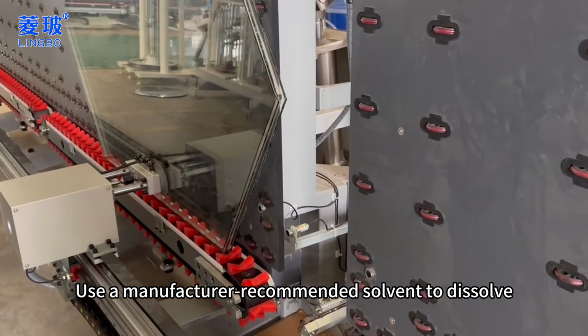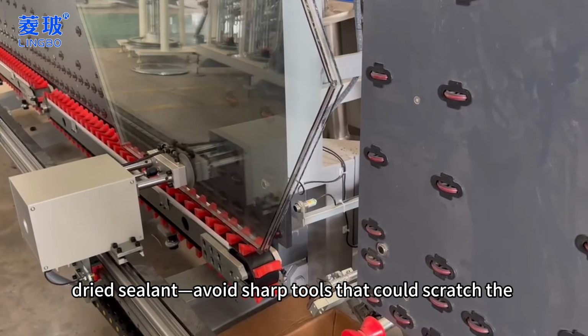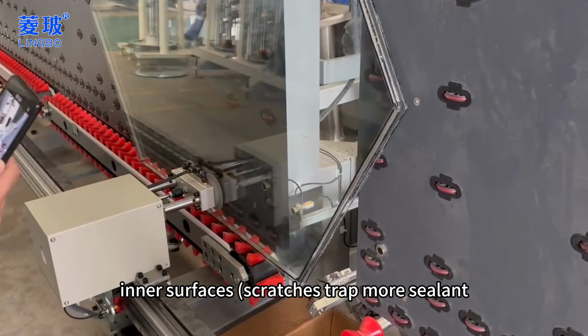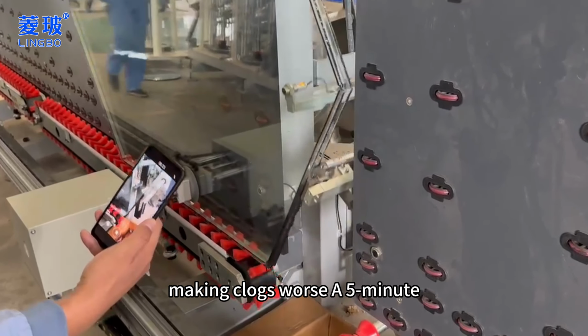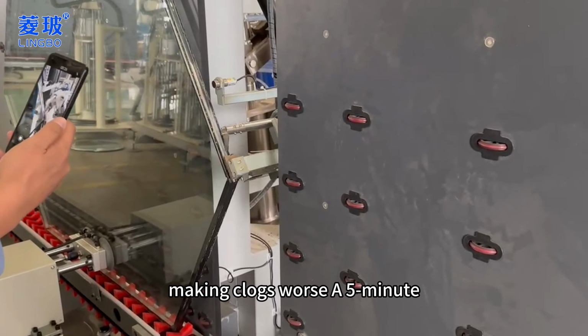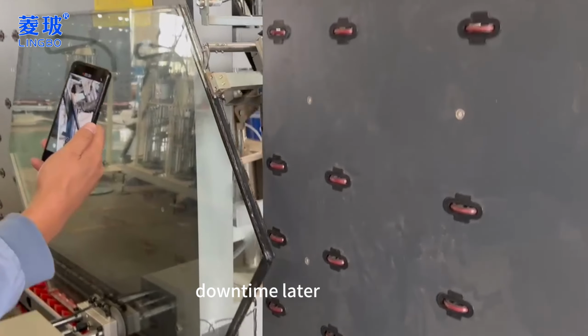Use a manufacturer-recommended solvent to dissolve dried sealant. Avoid sharp tools that could scratch the inner surfaces. Scratches trap more sealant, making clogs worse. A 5-minute cleaning routine can save hours of downtime later.